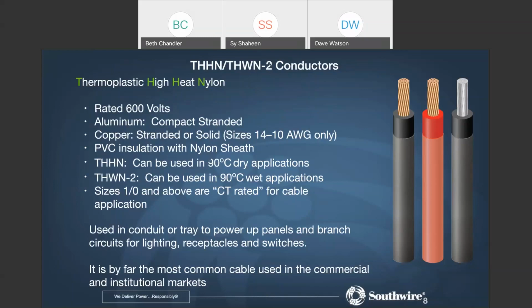The W in the designation indicates that it's rated for wet locations. All of the THHN conductors that we make are dual rated; some of the sizes carry more than two ratings, but we're going to focus just on these two. So they're all going to be rated for dry and wet locations. These conductors can be used outdoors, installed in conduit, and they cannot be direct buried, though. So they must be protected in some kind of a raceway. Next.